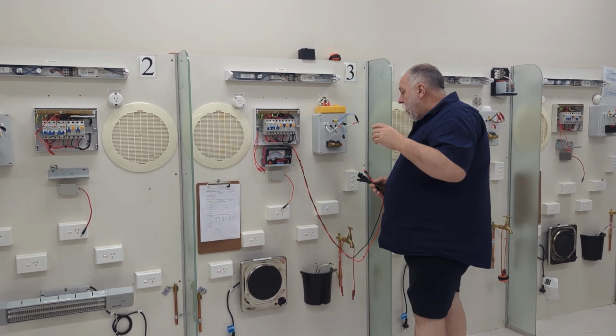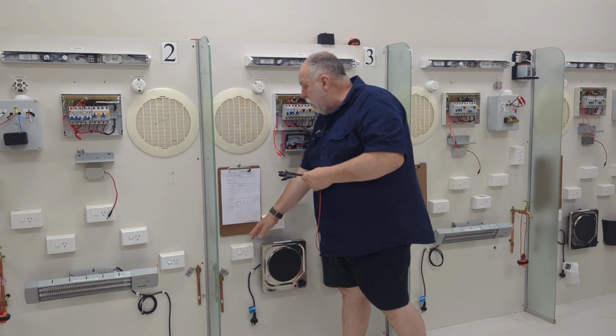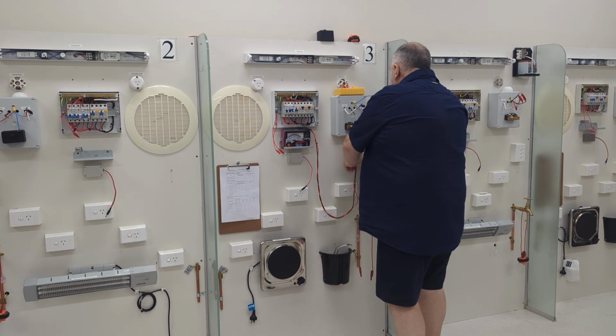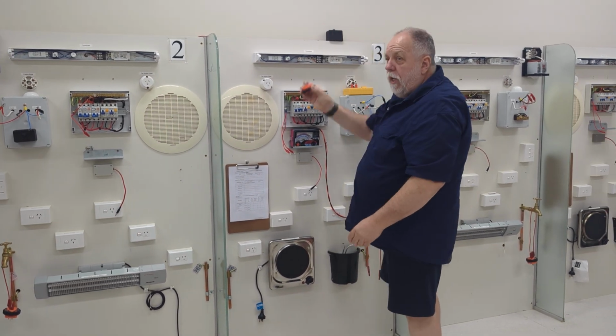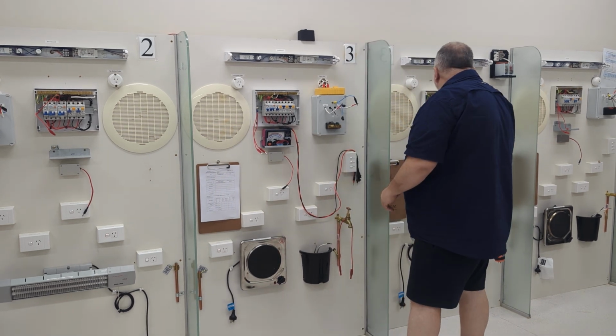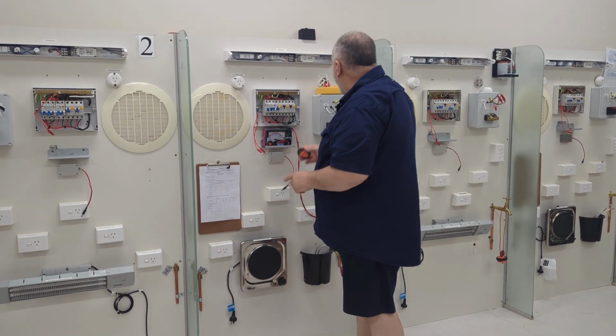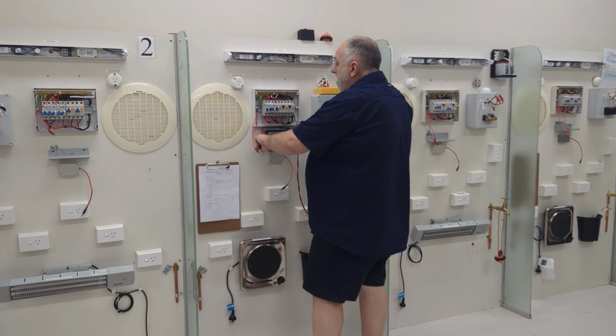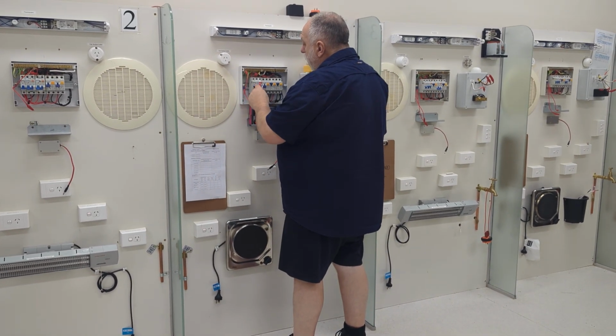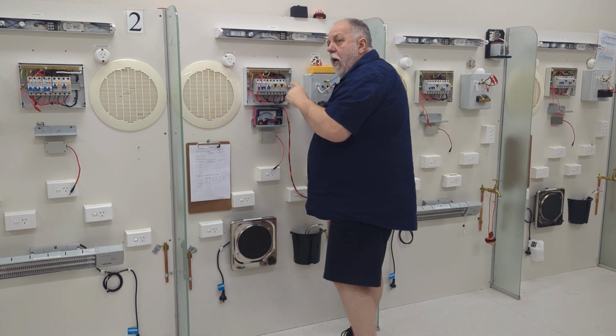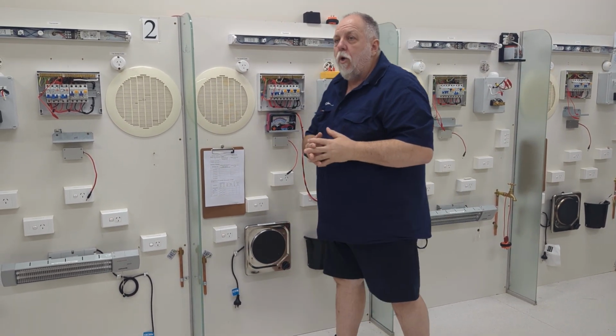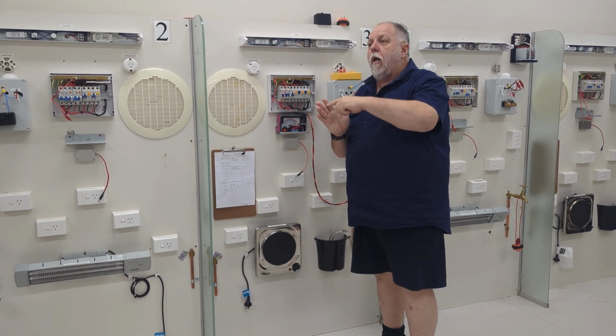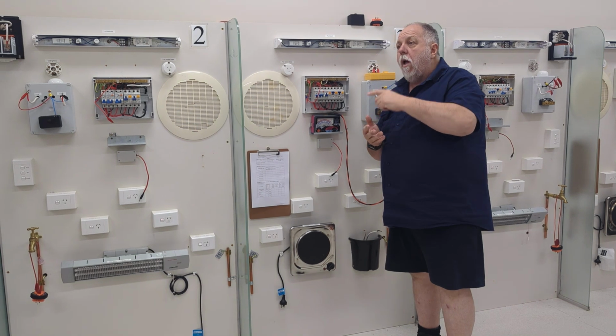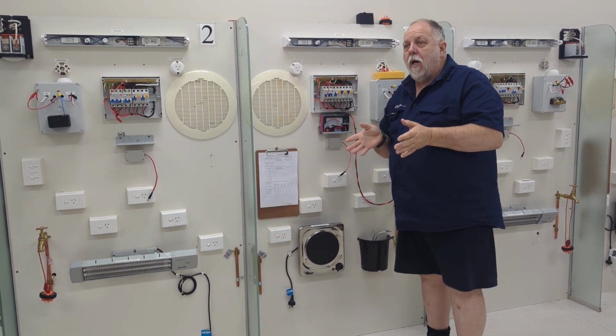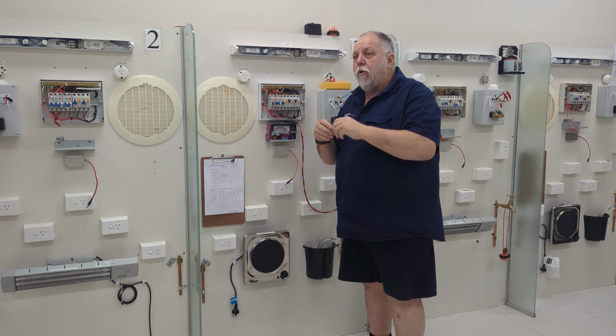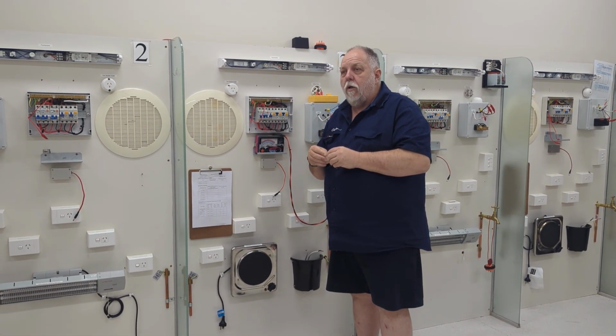automatic disconnection of supply. So what they mainly use it on, we're going to just do it on the appliance socket outlet. What they want you to do, you can either use this point here, plug this in, and put a short between the active and earth, right? But I'm going to do it at the switchboard. So what I'm going to do is put a short between the earth and the active. I now have the active and earth shorted. What we're doing is measuring the resistance from the bottom of the circuit breaker down to the appliance, back up to the earth bar, to make sure that resistance is not too high for Table 8.2, so that it will cause the circuit to operate.